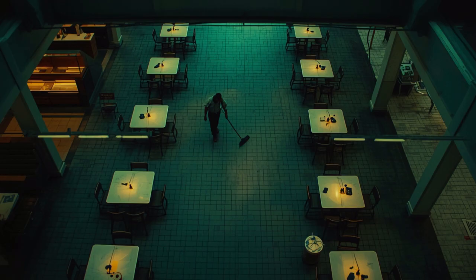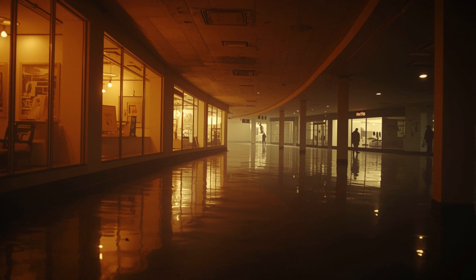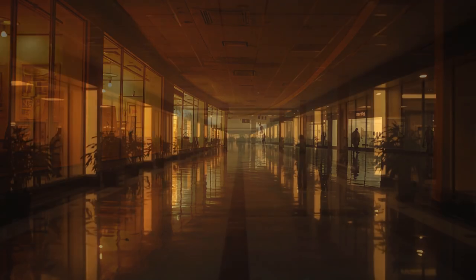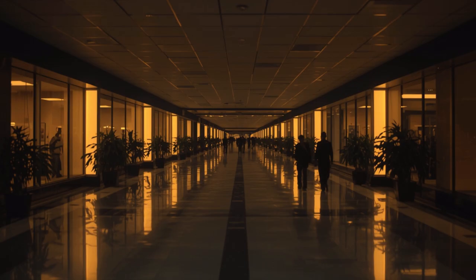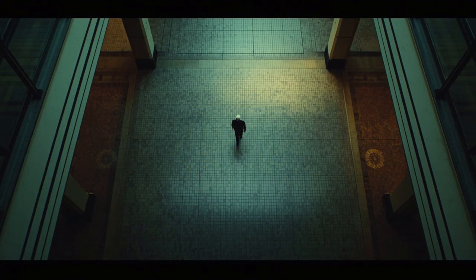The hot gases rising from a fire cool as they rise, entraining surrounding air and losing heat to the atrium volume, so that by the time they reach the ceiling of a 40 or 50-foot atrium, they may have cooled sufficiently that they no longer carry enough heat to activate conventional sprinkler heads. The sprinklers at ceiling level might not operate at all, even with a significant fire burning at the atrium floor 40 feet below. The engineering response to this problem involved several approaches.